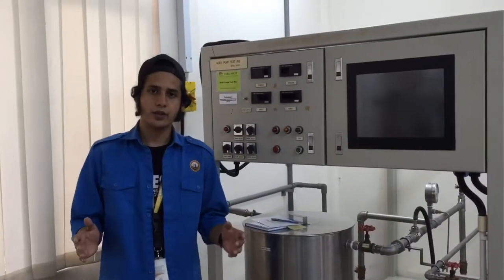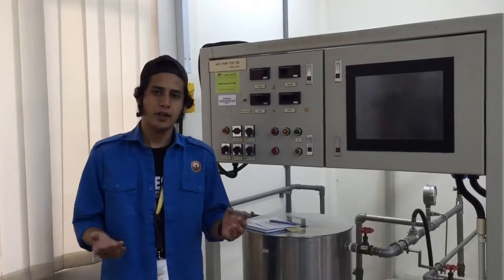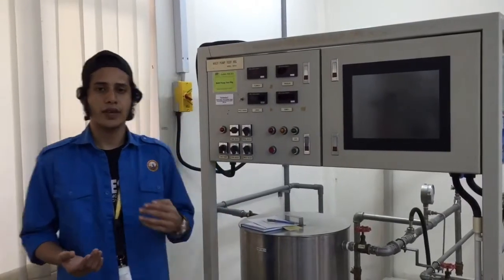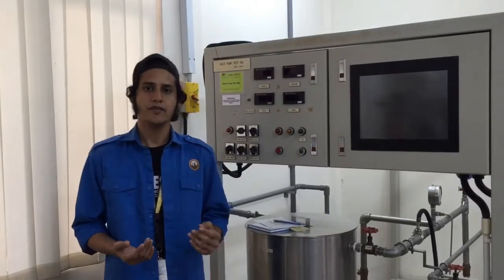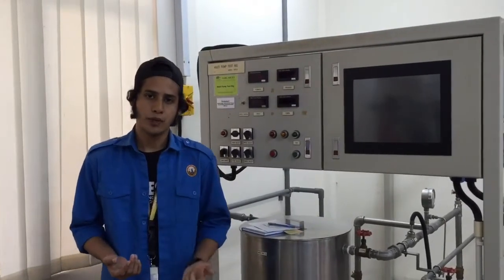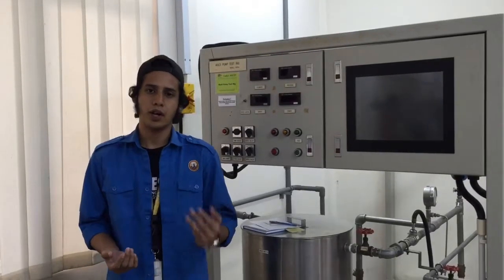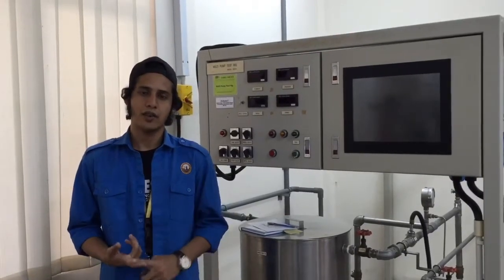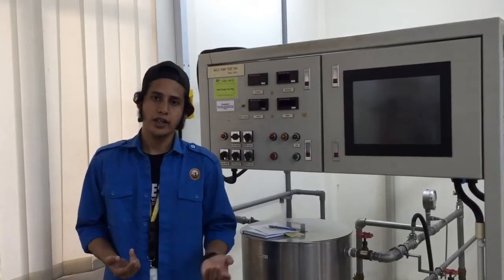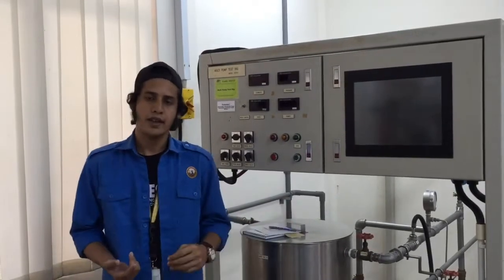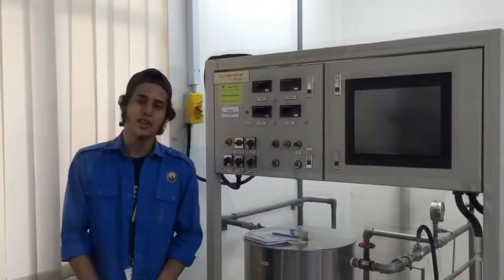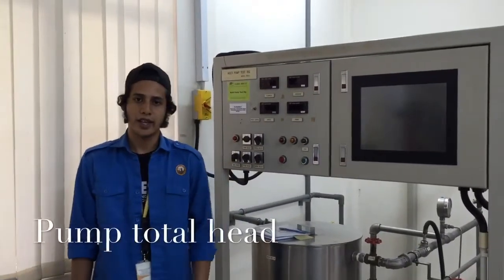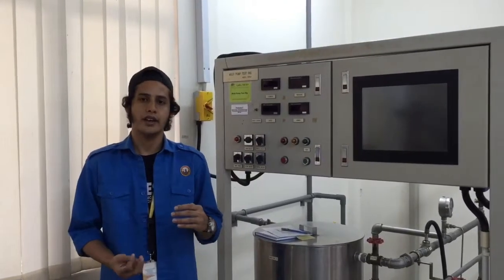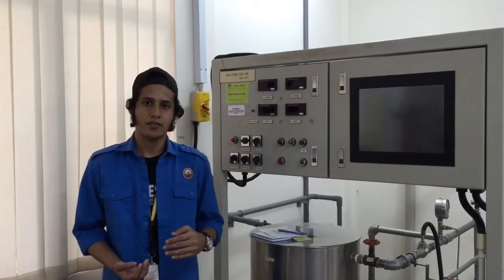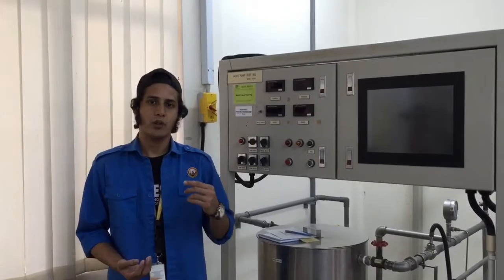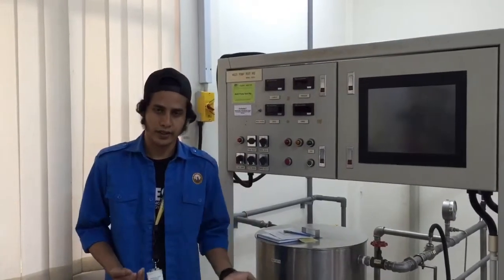In order to measure the characteristics of each pump, a few characteristics were taken into measure: pump total head, motor power input, pump power input, pump power output, pump efficiency, overall efficiency, and an additional one for the gear pump, which is volumetric efficiency. The first one, the pump total head, indicates the capability of a pump to raise water to a height from one point to another.